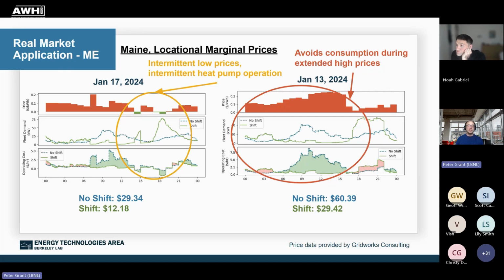January 13th in Maine showed an example of extended high prices running from about 5 a.m. to 4 p.m. The water heaters had enough energy storage that, with the advanced load-up signal increasing the set temperature, they were able to supercharge the tank during the low evening prices and coast through to the next afternoon when prices dropped again. This reduced operating costs by 51%.